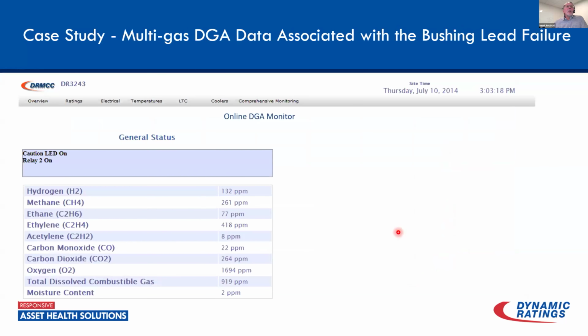Now, what's ironic here is you'll notice this happened somewhere around July 9th, mid-evening. Here's the DGA monitor. If we're looking at the DGA monitor, this is almost a day later. So it's almost like a cause and effect thing, where we had a problem. The partial discharge monitor identified a significant increase in energy. And then, about 20 hours later, the DGA monitor went into alarm. What's interesting is that we did have an increase in hydrogen, but I'd say that was a fairly moderate increase. If I'm tracking the trends, I may have gotten alarmed depending on how sensitive I was setting this, but it's really some of the other gases that were causing this, the methanes, the ethylenes, and things like that.